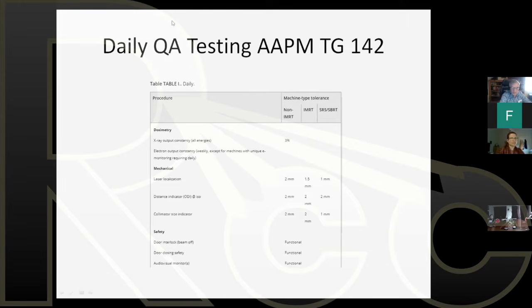So if the machine is being used for electron treatment, then the electron output must also be measured. Mechanical tests are important, and as you can see, the mechanical tolerances vary depending upon what the machine is used for. There's laser localization, the distance indicator, the ODI, optical distance indicator, and also the collimator field size indicator.